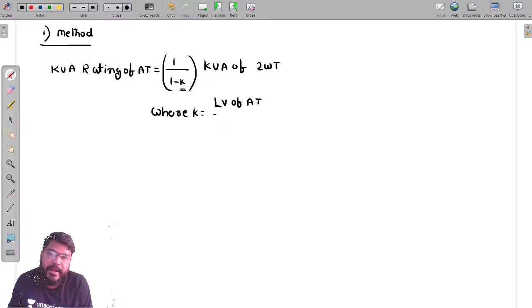See here, we were given 600 and 720, so this is the low voltage of the auto transformer, and this 720 volts is the high voltage of auto transformer. Got my point? So low voltage of auto transformer divided by high voltage of auto transformer. Now find out, low voltage is 600 divided by high voltage is 700... 720 volts. So now kVA rating of auto transformer.